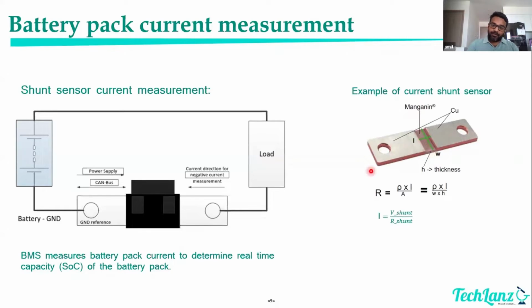What equation do we use to determine the current? Current is proportional to the voltage developed across the shunt element. There will be a shunt element like this, and the BMS measures the voltage drop across two terminals on the left and right side that go into the BMS. This voltage difference across the manganin element is proportional to the current flowing through it, and based on that, the BMS determines how much current is flowing through this resistive element.